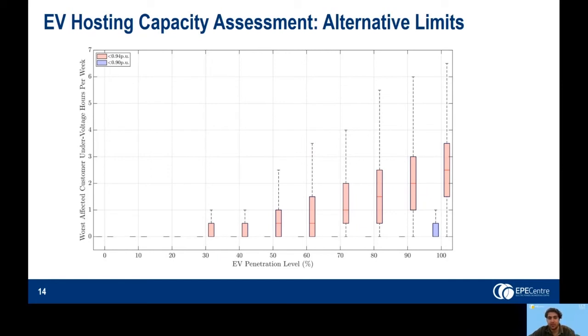At each penetration level, the box plot shows the distribution of results across all Monte Carlo repetitions. The right-hand side box plot is the number of hours below the 0.94 per unit threshold. The left-hand side box plot is the number of hours below the 0.9 per unit threshold. It can be seen that higher numbers of undervoltage hours are more likely at higher penetration levels. Furthermore, minor undervoltages, that is those less than 0.94 per unit, are significantly more common than major undervoltages, that is those less than 0.9 per unit.